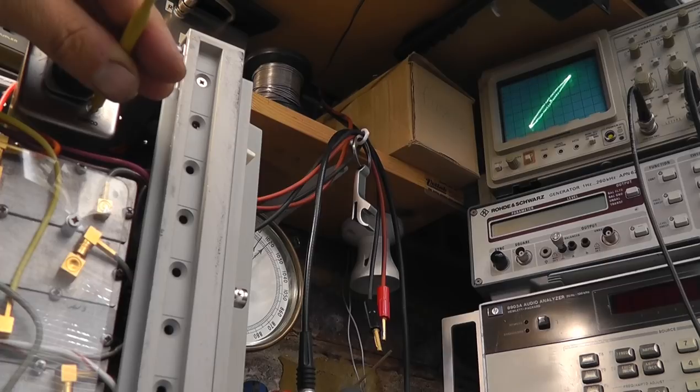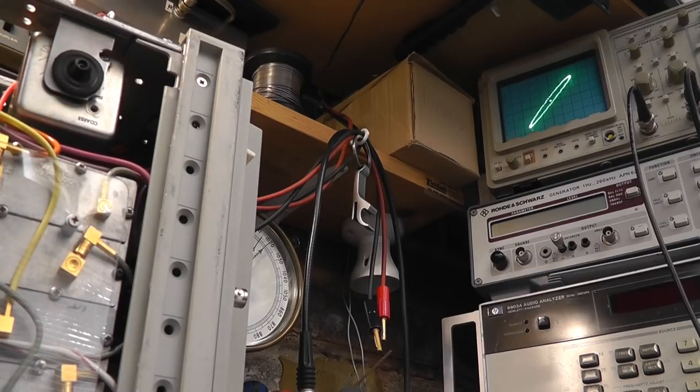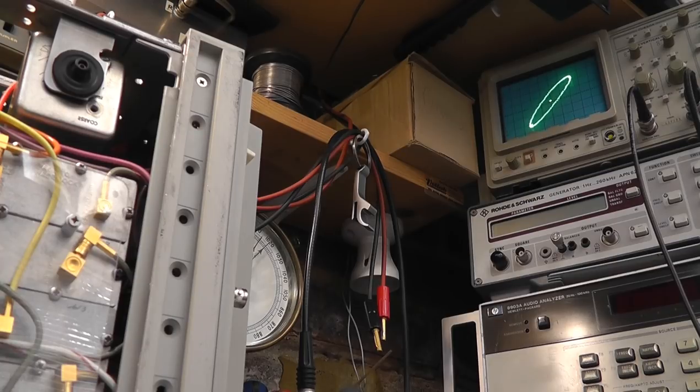It's just over about seven minutes since the last clip. You can see it's actually stabilized now but it's obviously moving too fast, about one hertz fast or slow. Let's just bring that in and then we can put this back together again. We want a stationary circle really or stationary trace. This is the coarse adjustment I'm doing now so this is a bit jumpy. That's pretty good actually, that's pretty stationary. That's the sort of thing we're looking for. I'm going to leave it running for another half an hour and then adjust the fine adjustment if it needs any but I think that's pretty good.